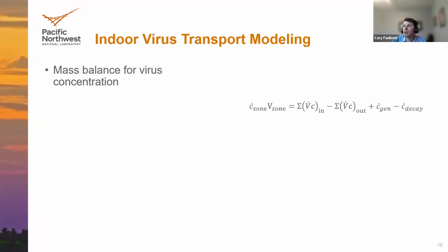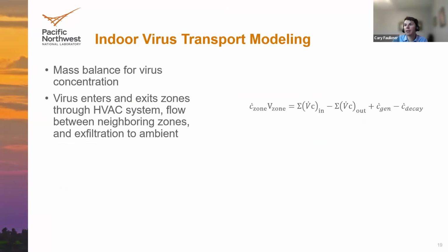We also add some indoor virus transport modeling. So we're going to start from the mass balance for the virus concentration within the zones. And this describes the rate of change of virus concentration, or some sort of biological pathogen concentration, within the zone. In this case, the virus can enter and exit the zones through the HVAC system, where it might be exhausted to the ambient environment or recirculated, but filtered and returned to the zones. There's also going to be some airflow modeled between the neighboring zones and exfiltration to the ambient.